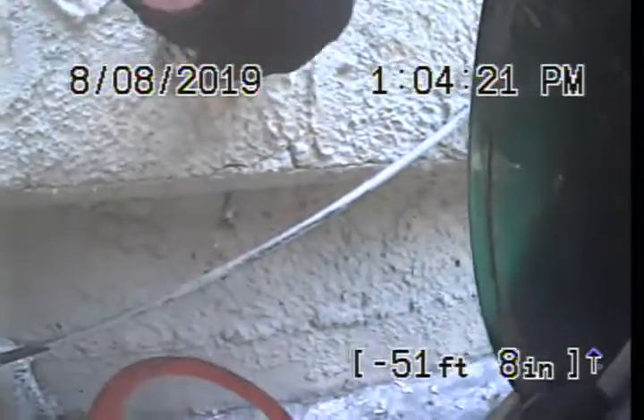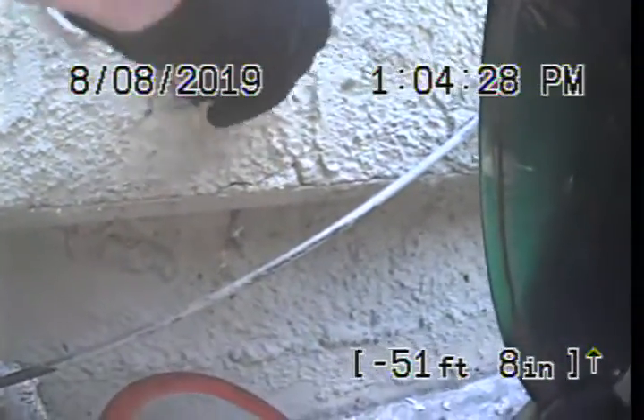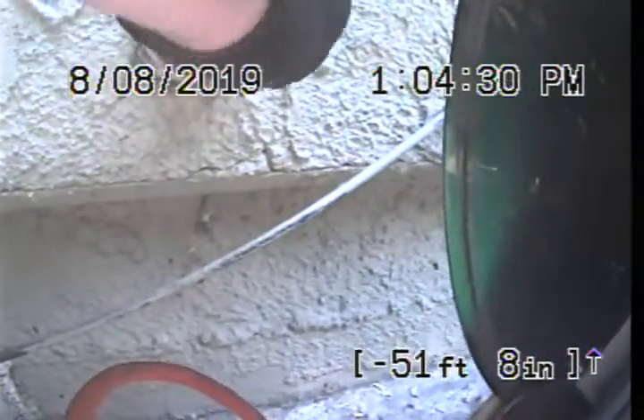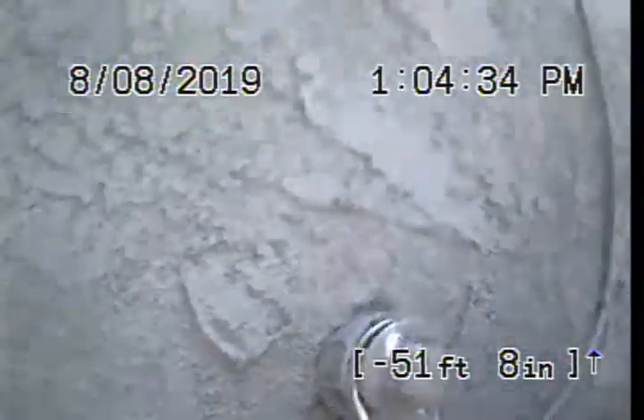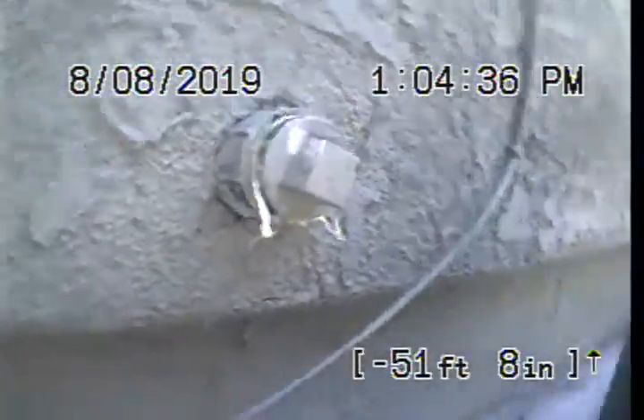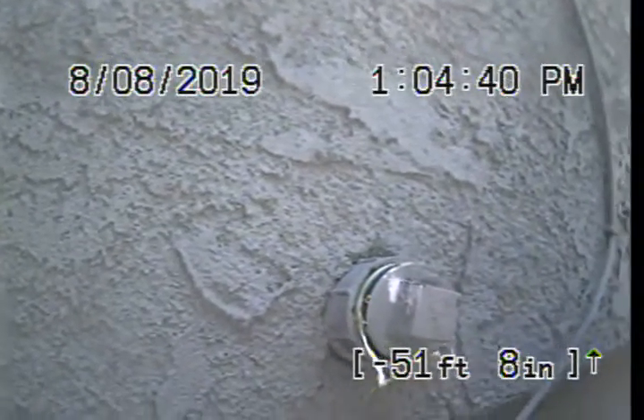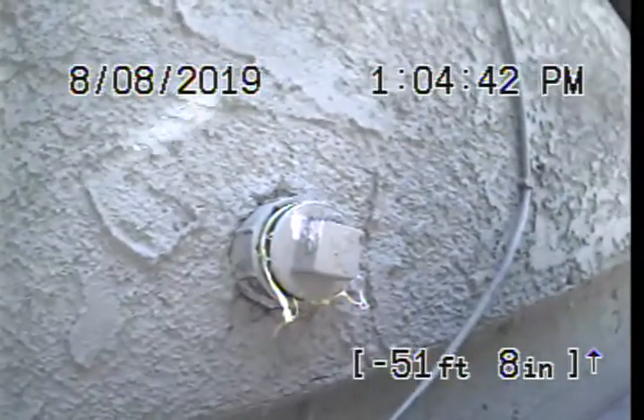But essentially, my recommendations at this time are going to be to get that section, it's about a 7-foot section under the house, fixed, the building drain line system that's currently holding water. I will also be recommending that a main sewer line cleanout gets installed. It's something kind of standard to have, especially with the clay pipe outside. With the necessity to clean it, you're going to want to make sure you have an access point to that.